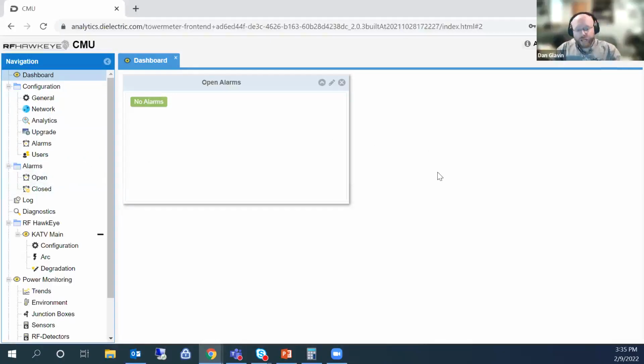When you first log in to the unit, you come to a dashboard, and this dashboard is configurable based on the measurements or sensors that you have connected to the RFHawkeye. Currently, this dashboard just shows open alarms. Everybody loves to see no alarms in green - that means there's no localized degradation in the transmission line, there have been no arcs in the last 24 hours, and the antenna VSWR is within an acceptable value and beneath a warning threshold.